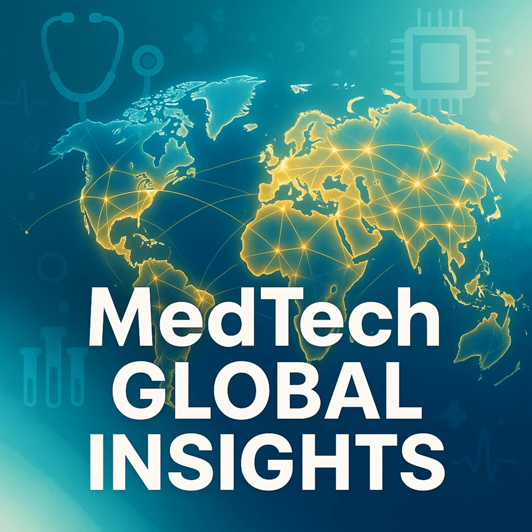For example, a company developing an AI for diabetic retinopathy screening faced major delays because their training data was sourced predominantly from one ethnic group. This raised valid questions from the notified body about the algorithm's accuracy across a diverse European population. You must also address the black box problem. You need to explain the logic of your AI, detailing its architecture, key parameters, and the robust validation methods used to ensure its safety and performance.